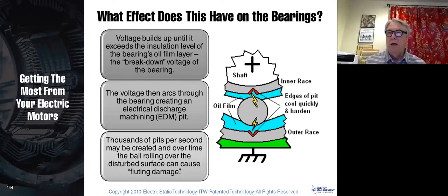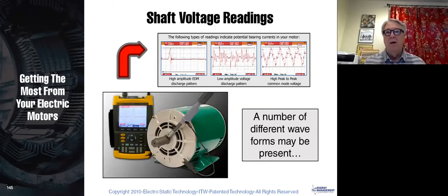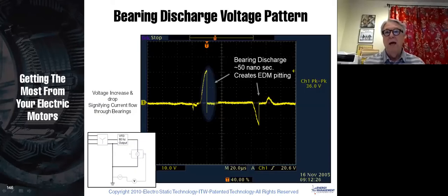And when it does that, it goes from the inner race through the film, through the ball, through another of the film on the other side, and then the outer race. And it's like welding on your ball bearings. So not good. This is a picture of the common mode voltages when we're measuring them between the frame and the shaft of the motor. And this is a close-up of that.